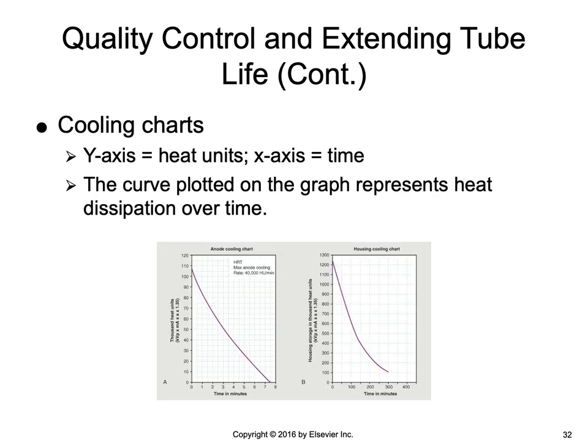The anode cooling chart and the housing cooling chart both work the same way. The anode cooling chart is used to determine the time it takes for the anode to cool based on the factors given, and the housing cooling chart does the same for the tube housing. The y-axis represents heat units, usually expressed in thousands, and the x-axis represents time in minutes. The curve plotted on the graph is the cooling curve, representing heat dissipation over time — basically how long it takes for the tube to cool.